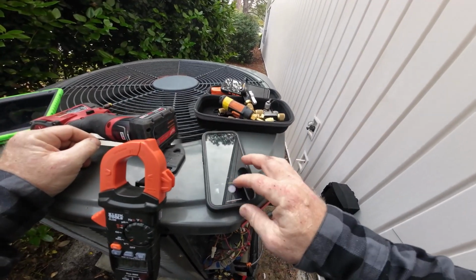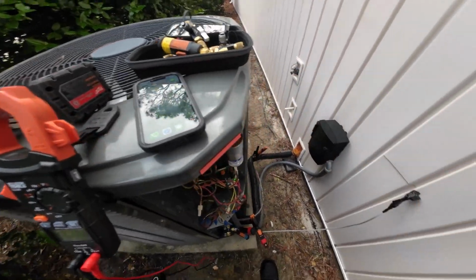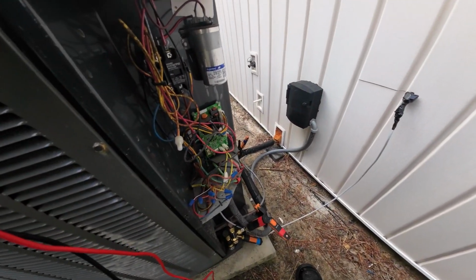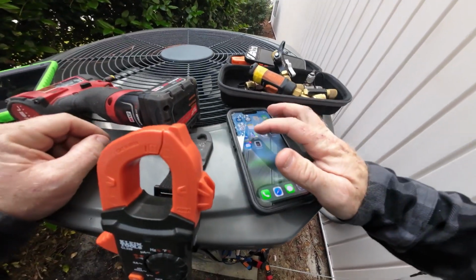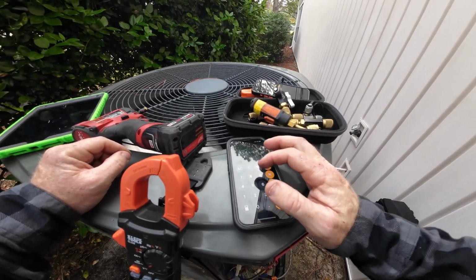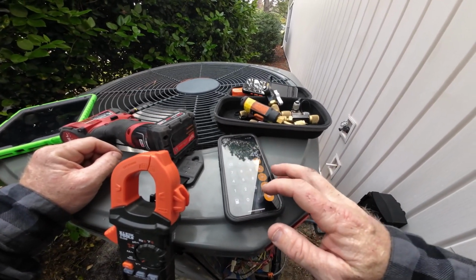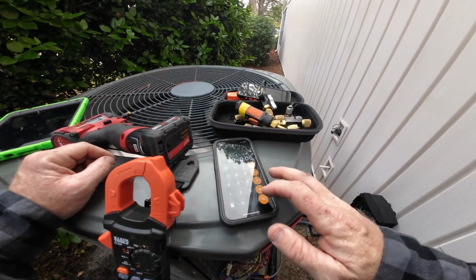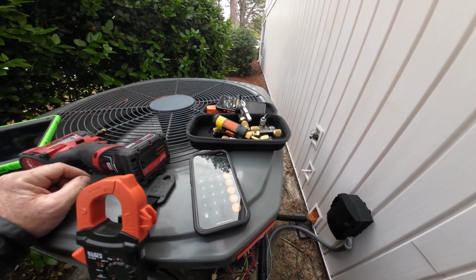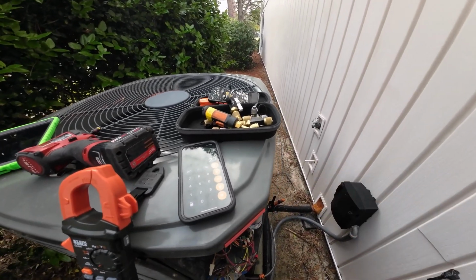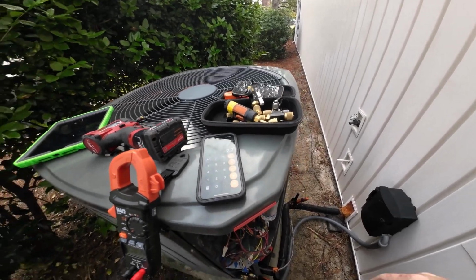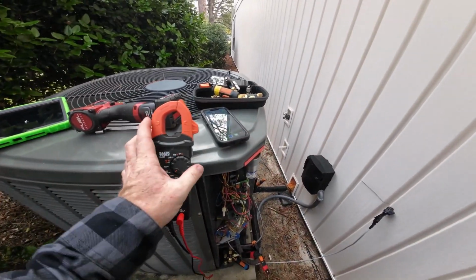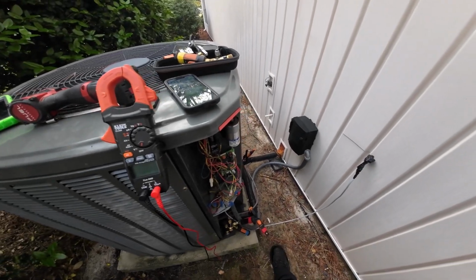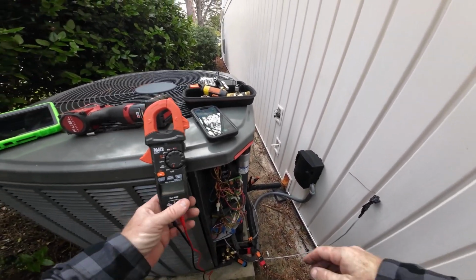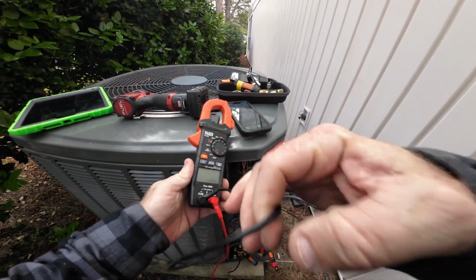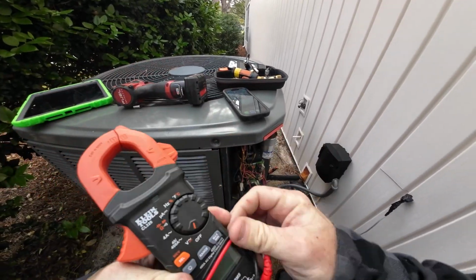So it says plus or minus 6%. So then I'll do a calculation. 45 times 0.06 is 2. So this capacitor is past its threshold. So I'm going to recommend a new capacitor. And then we're going to get my leaf blower. We're going to blow all this out.